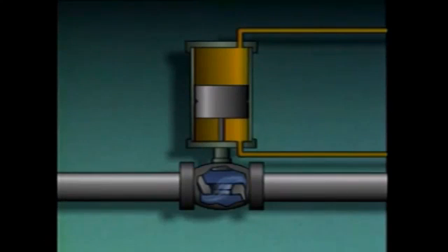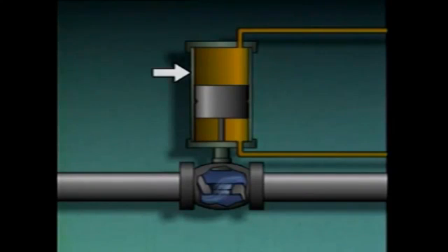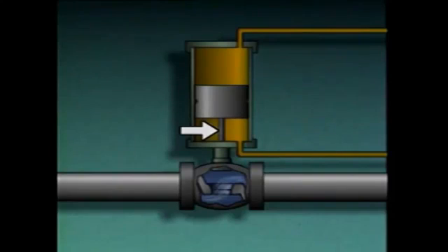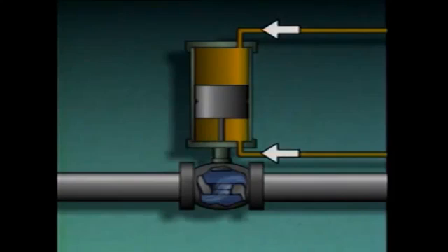A double-acting hydraulic actuator is called double-acting because it uses hydraulic fluid pressure to both open and close a valve. It consists of a cylinder, a fluid port at the base, a second fluid port at the top, a piston, and a piston rod connected to the valve disc. Fluid can enter the cylinder through either of the two ports to move the piston up or down.